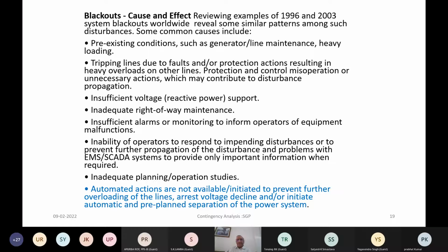Usually the forced outages of any line, suppose for example, a line had to be taken out in spite of the loading of the transmission corridors because some clamp is becoming hot. So an emergency forced outage is required to be taken. So it results again in a double contingency, because the system is already loaded and then you are required to take one more line outage. Or sometimes there is a pre-existing condition where the line is out for major maintenance or construction activity, or some reconductoring activity, or sometimes you do loop in, loop out, or a conductor replacement, etc.